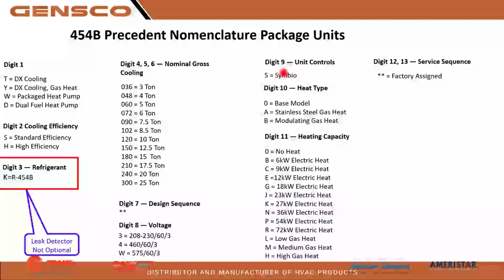And S is for Symbio, so digit 9. There are still some E for electromechanical. E is just straight up 24-volt system. Any thermostat can work on it. Any thermostat can work on this too. Zone sensors are the best to utilize the efficiency of it, but any 24-volt stat can work.